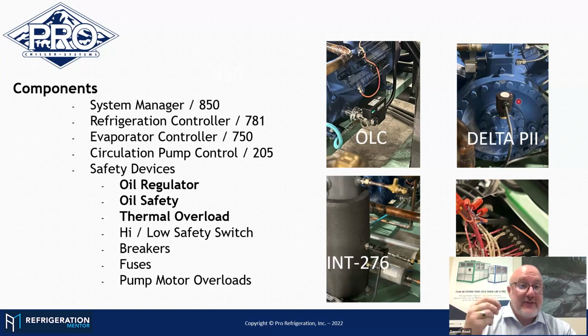If you walk up to it and it's just flashing rapidly, that's telling you that you've got an oil sensor issue, so something's not happy with the sensor. On the oil reservoir, that's where we distribute the oil to both of the compressors.